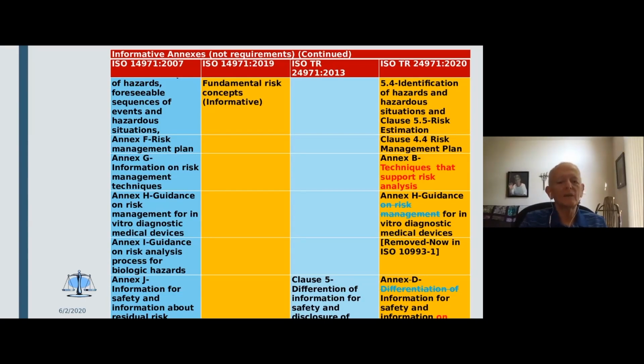Annex H was the guidance on IVDs. It remains Annex H in the new document. So those of you that are doing IVDs, it's the same place, but just in the TR instead of in the standard. And we deleted "on risk management" from the title and just shortened it a little bit. Annex I is guidance on risk analysis process for biological hazards. That was totally removed because the folks that wrote ISO 10993, the biologic hazards standard, in -1 covered that topic exceedingly well, better than we could have. So we just deferred to them for their expertise, and they did a great job on that one.